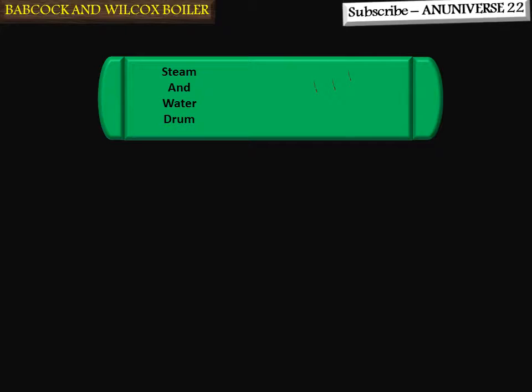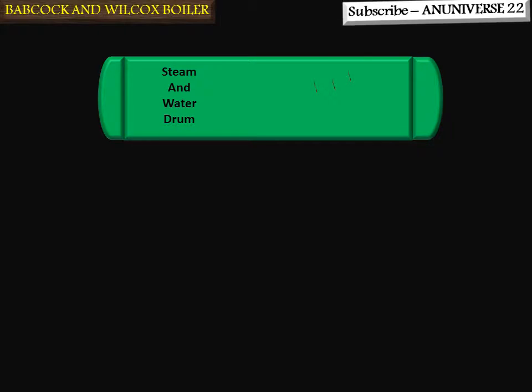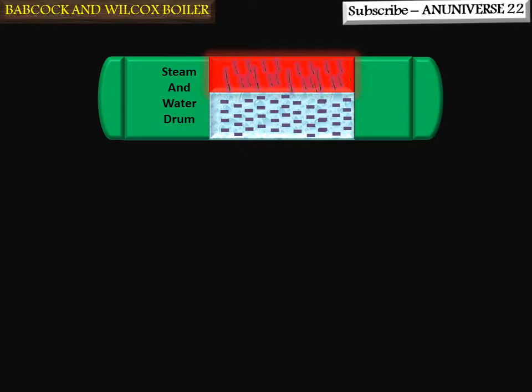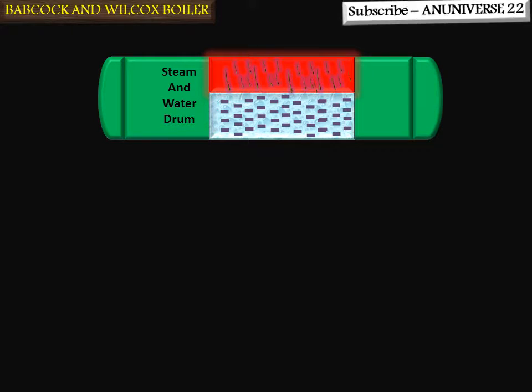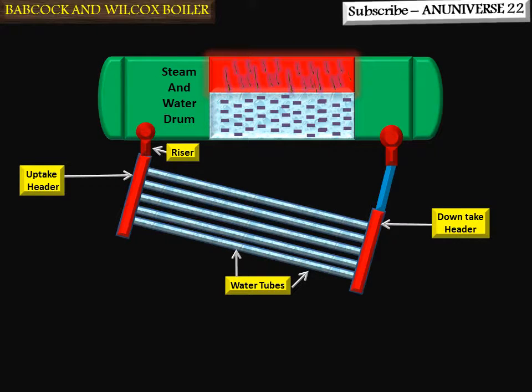Now we will discuss the construction of the Babcock and Wilcox boiler. It consists of a steam separator drum that is mounted at the top, in which water and steam are placed together. One half of the drum is filled with water and the other half is remaining for steam. It is connected by an uptake header and a downtake header, and a large number of water tubes connect the uptake and downtake headers. The water tubes are inclined 5 to 15 degrees to promote water circulation.